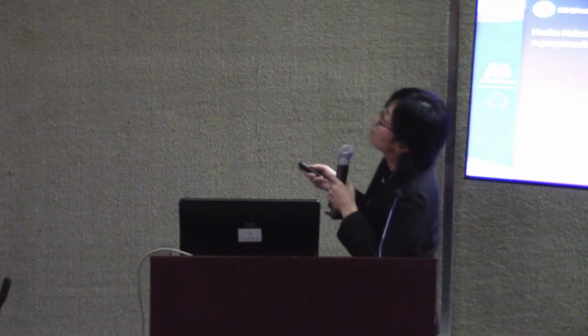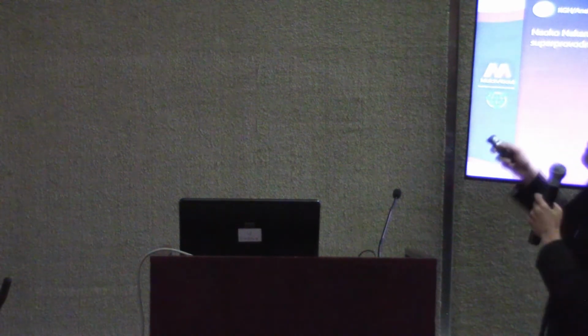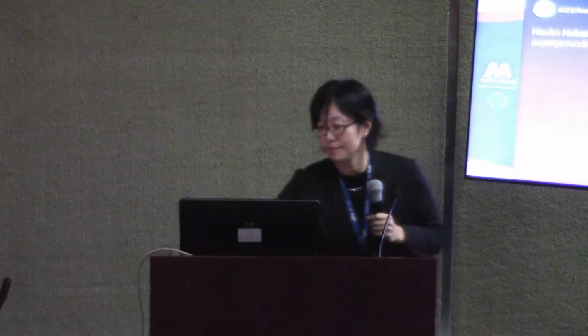The HTS superconducting cable system is located in a substation of Yokohama. This is the layout in Yokohama. This is the layout of a superconducting cable system. This is a cut model of the superconducting cable. The superconducting cable is cooled by liquid nitrogen. Liquid nitrogen flows in this area and is circulated through the superconducting line like this. This is the cooling system flow. Liquid nitrogen is circulated by a centrifugal pump and cooled by the refrigerator to keep the subcooled state of the nitrogen.